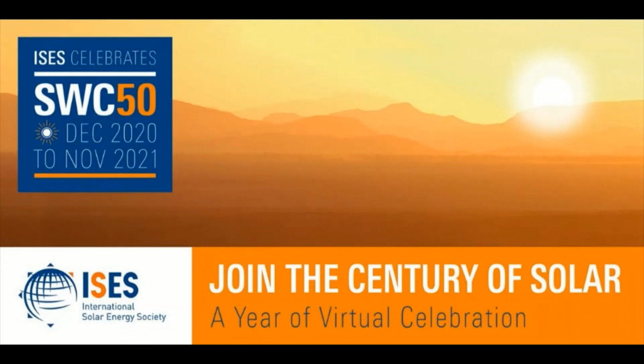I hope in the future there will be a version for PV cooling too. But what's more interesting, and what I want to summarize, is that we should also look into hybrid systems in solar cooling, because that's the new kind of technology popping up now. It's a combination of a compressor chiller with an absorption or adsorption chiller in one system, usually in one shell, where you can use PV and solar thermal as input to run such systems at very high efficiency. You can achieve EERs, energy efficiency ratios, above 8 to 10 for the overall system, especially in hot climates. That's really an improvement from a technical point of view, where we can use renewables to improve the already existing compressor technologies through this kind of combination.